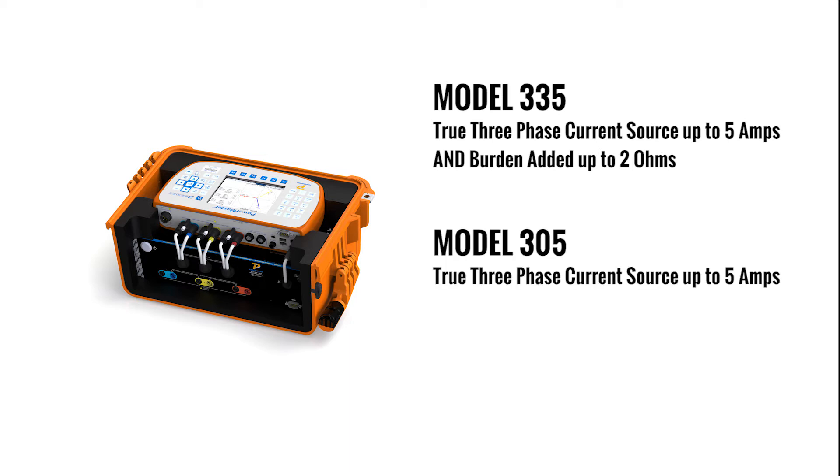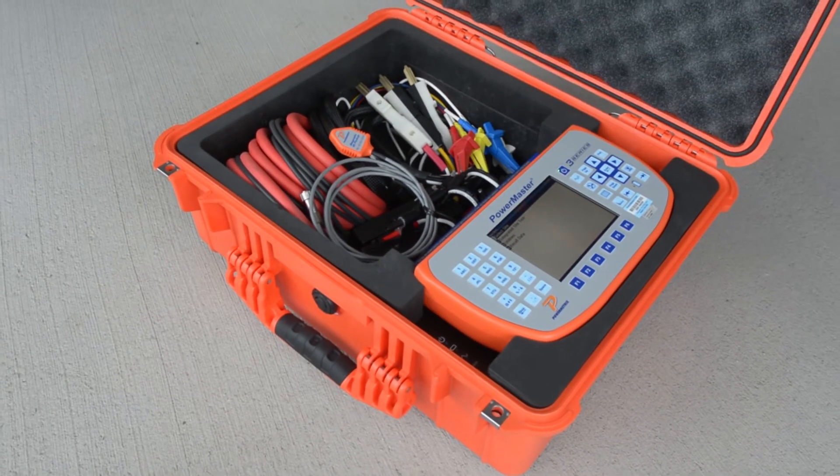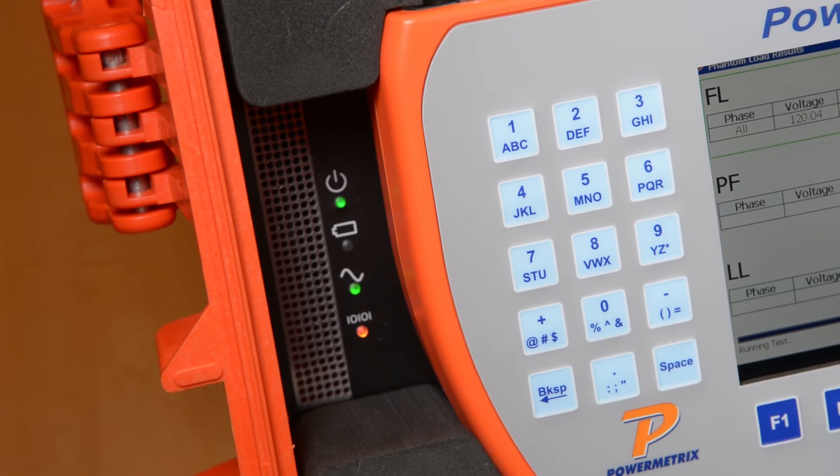The Model 305 offers a true three-phase current source up to 5 amps per phase for ANSI meter testing. The Model 335 offers burden-added up to 2 ohms in five steps for CT testing. All of these models fit neatly into the integrated carrying case of the 3302. They are also battery-powered, so there is no need for an auxiliary power source, even when sourcing current.